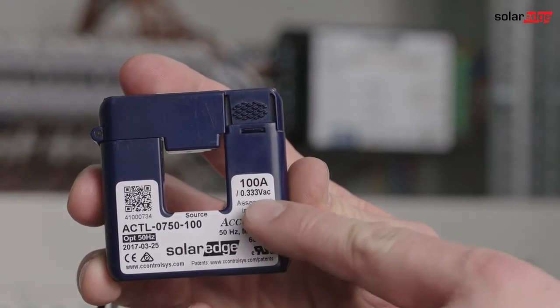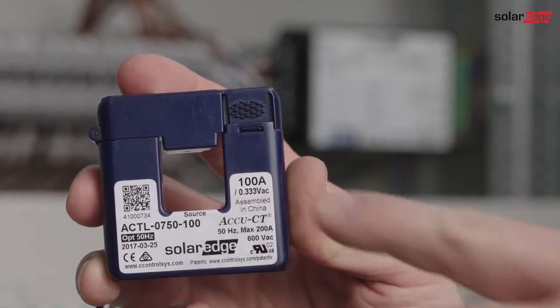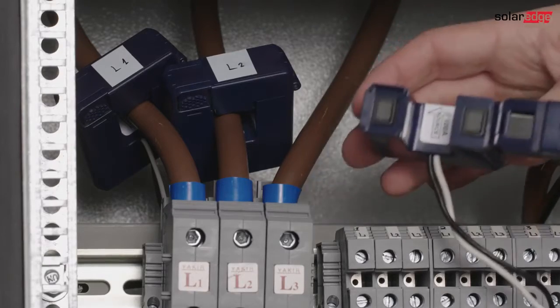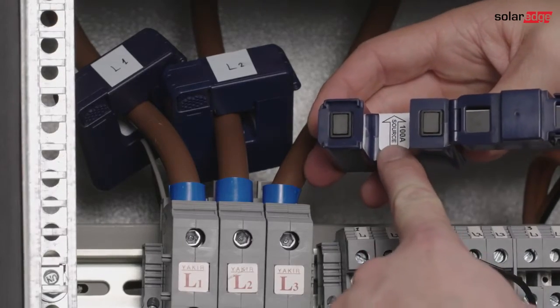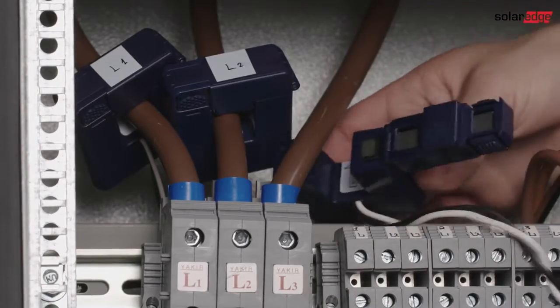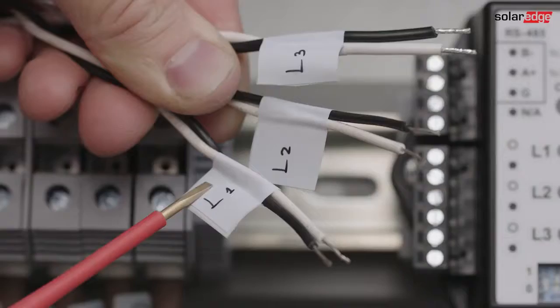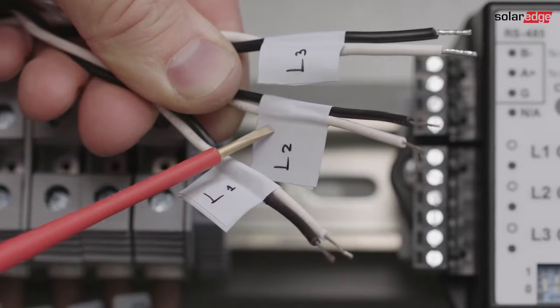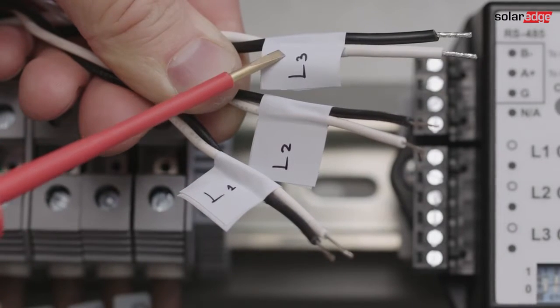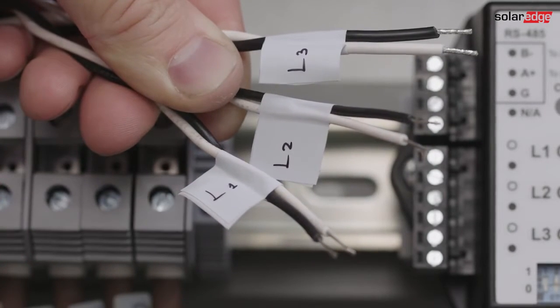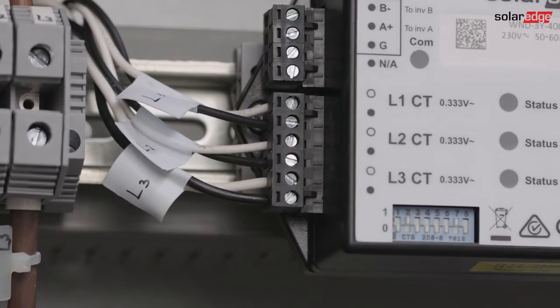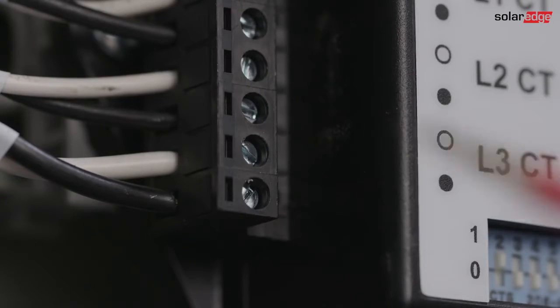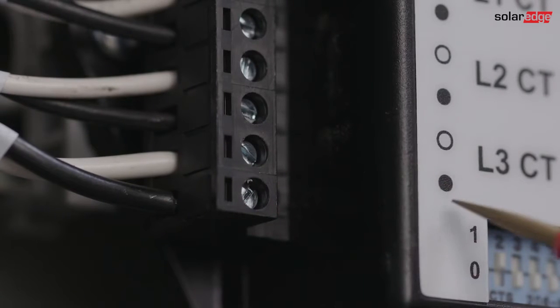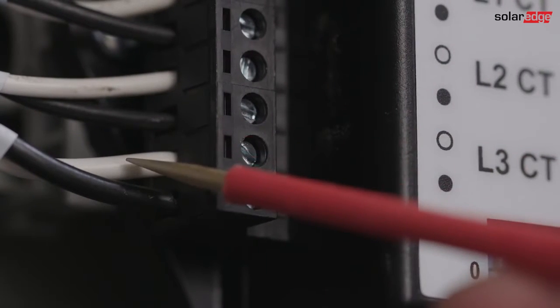Each CT clamps around one of the main power supply's phase wires. They should be installed at the grid connection point, and the arrow on the CT should point toward the grid connection. Make sure to keep the CTs in the same order as the AC wires: L1 CT to L1 phase, and so on. The CT wires have a certain polarity. Make sure to connect the black and white wires according to the black and white dots on the meter's label.